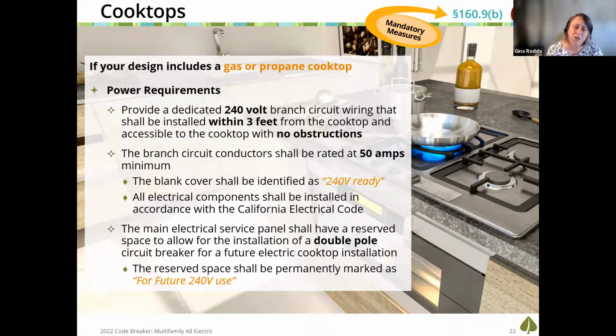So if you decided to go with a gas furnace and a gas cooktop, that's a 30 amp plus a 50 amp. These are separate from each other. You don't get to reserve one and say, okay, they might do either a furnace or a gas stovetop. Each of these will have its own branch circuits and wiring. And at that main service panel serving the dwelling unit, another double pole circuit breaker for the future electric cooktop.